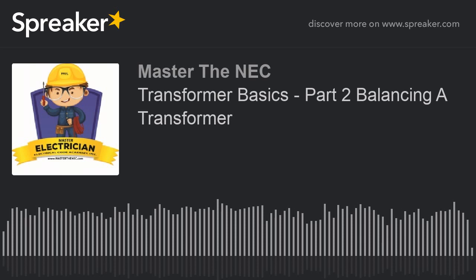So I'm going to put under C1 two of them because I got 3. I'm going to end up putting 2 under 1 anyway. So I'm going to put 2 of them under C1, which is going to be 8 kVA, and I'm going to put 1 of them under C2's value for the kVA. So I'm going to put 4 kVA or 4,000 VA under C2.